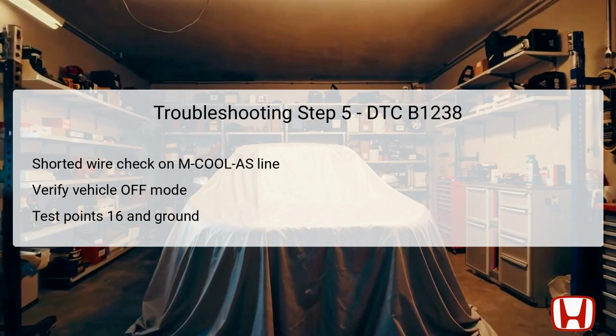Continuing with the troubleshooting, the next step involves checking for shorts in the MCOOL-AS line, similar to the previous step. Ensure the vehicle is in the off or lock position and all relevant connectors remain disconnected. Testing continuity between test point number 16 on the climate control unit and a body ground allows assessment for any shorts. If continuity is detected, this indicates a short to ground in the MCOOL-AS wire, which should be repaired immediately. If there's no continuity, it indicates that the MCOOL-AS wire is acceptable and functioning as intended. Concluding this phase of the troubleshooting protocol.